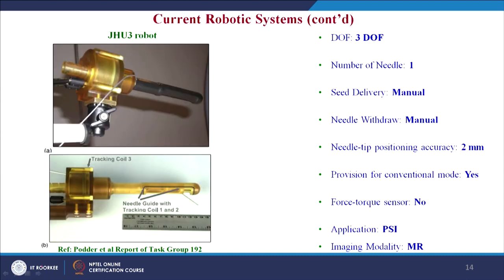The third Johns Hopkins system — from the Engineering Research Center and Department of Mechanical Engineering — is a remotely actuated manipulator for accessing the prostate tissue under MRI guidance. It has 3 degrees of freedom, one needle, and both seed delivery and needle withdrawal are manual. Needle tip positioning accuracy is 2 mm. The system has provision for conventional mode, is not equipped with a force-torque sensor, and the application is prostate seed implantation using magnetic resonance imaging.